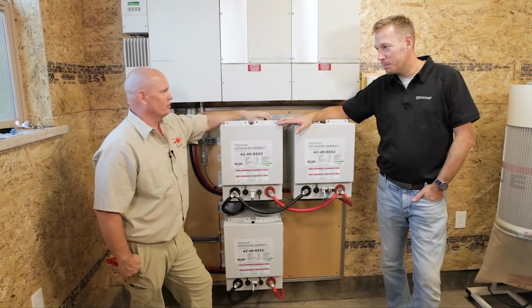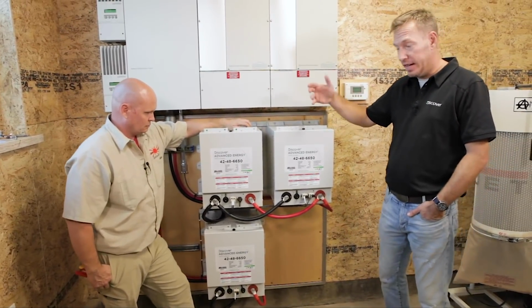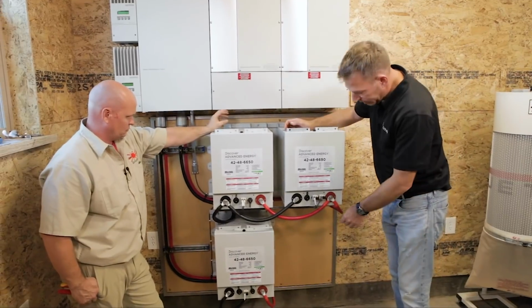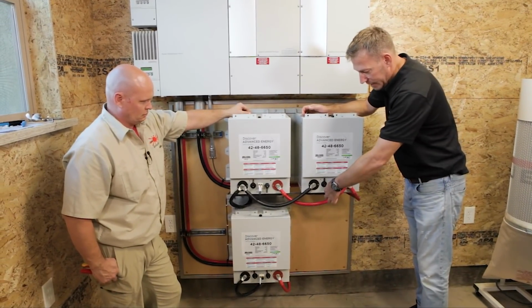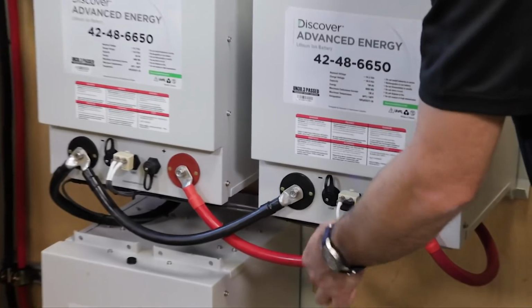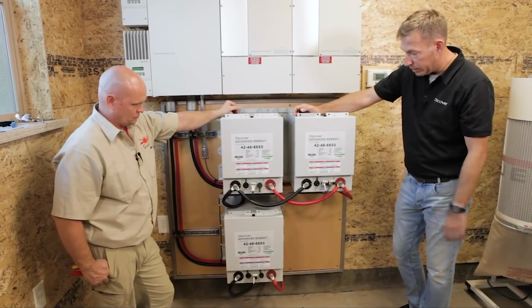All right, there we go. How'd we do? Looks amazing. Got to tell you some of the attention to detail that you don't see in every install. Now, granted, I'm used to seeing these things on the floor in the lab where the guys are doing quick connects and the like, but color coded with heat shrink on the two different networks. So you got AE bus in white, you've got the Xanbus in with black heat shrink, right? All of it's tucked back instead of looping over as a big tripping hazard or a snag hazard and the like. It looks beautiful. You did beautiful work.